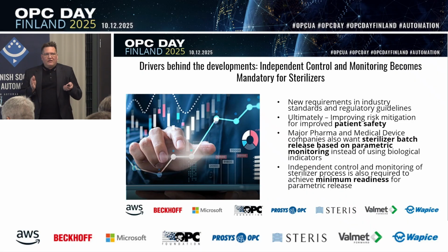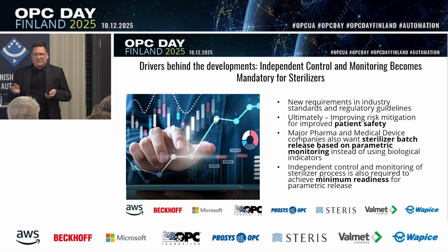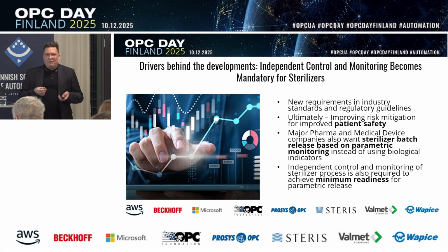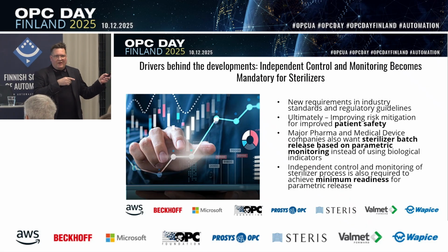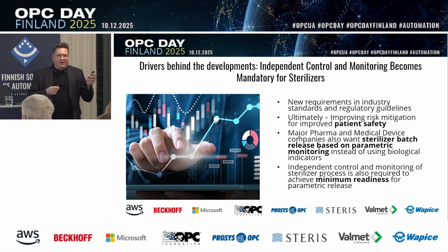One big driver for many large pharmaceutical and medical device manufacturers is moving towards parametric release of your sterilizer batches. This means that instead of relying on a biological device that must be destroyed so the organism is no longer alive, you would only validate your equipment against that biological organism placed in the most difficult location to sterilize, and then you look at the established parameters.